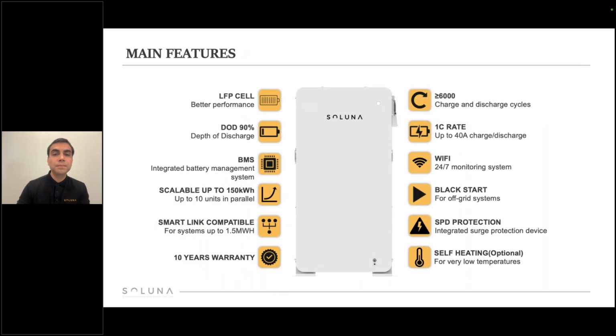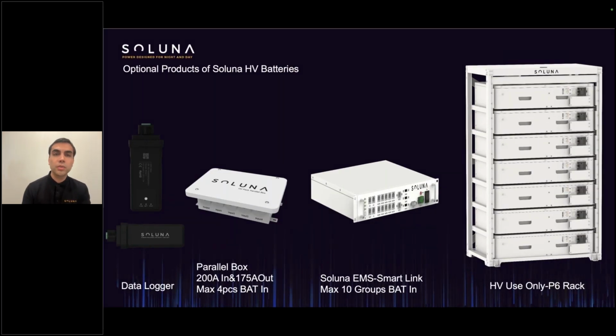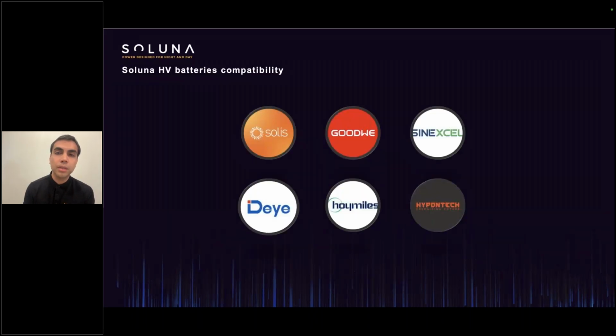It has a 10-year guarantee. The only thing we ask is that if there is an issue with the battery, as soon as you know, we ask that within at least 3 months you reach out to Soluna or your distributor, BayWa, and tell them there is a problem so that it can be covered by the guarantee, which will cover the freight and everything. And it has a self-heating option. And these are the optional products of Soluna for the high voltage: the parallel box, the data logger, the Smart Link, and the rack for 6 slots. It has compatibility with multiple inverters, but it's certified UL 9540 with Solis.